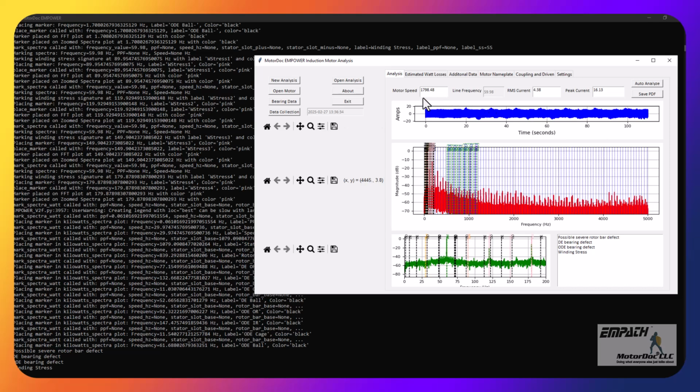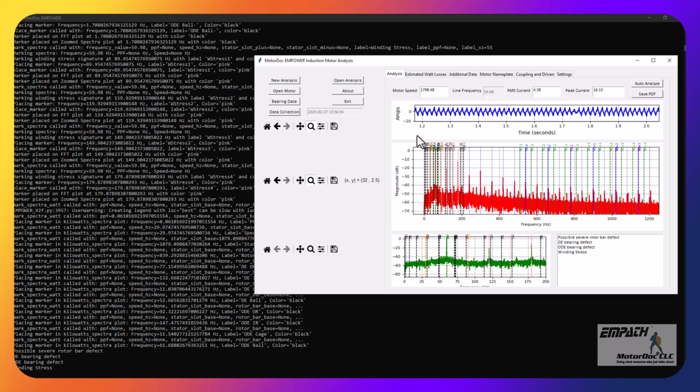You can see the RPM here. So it's estimating that it's an unloaded machine. This current is way high, so it's going to tell us it's overloaded, that kind of thing. I can come in and zoom in on any of these in order to see stuff. This is the zoom. I highly recommend that you experiment with the different buttons. See, here we go.